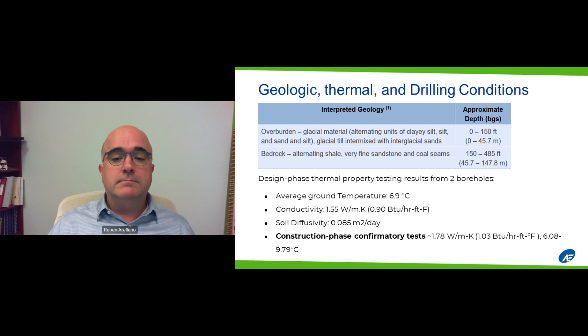We do a detailed look at the ground thermal properties. There's some thermal properties testing done before the design as part of pre-design feasibility work. Then during construction on a field of this size, we do additional confirmatory testing to update our thermal design models to a more representative set of thermal properties for the ground—looking at temperatures, conductivity, and thermal diffusivity as well.